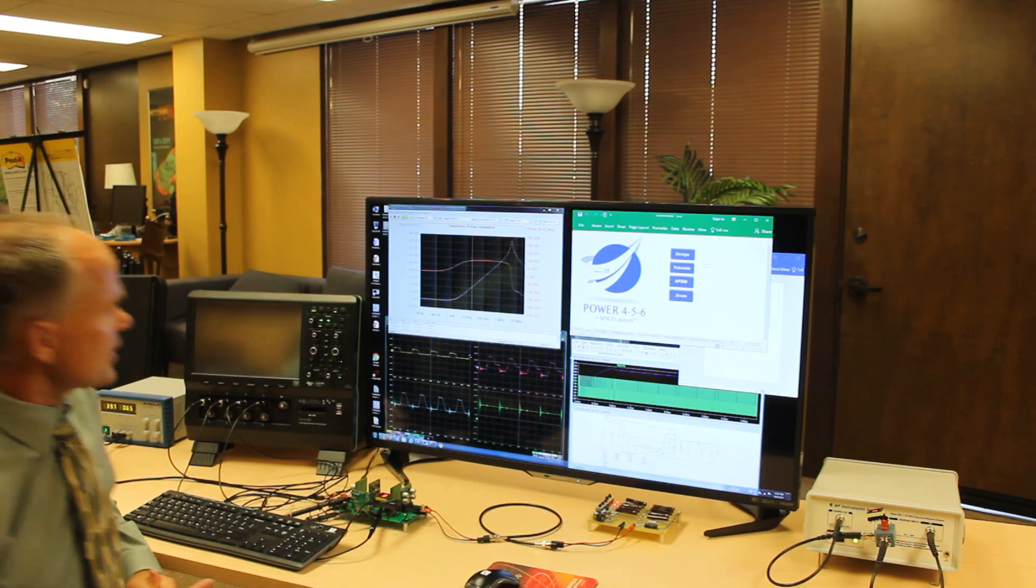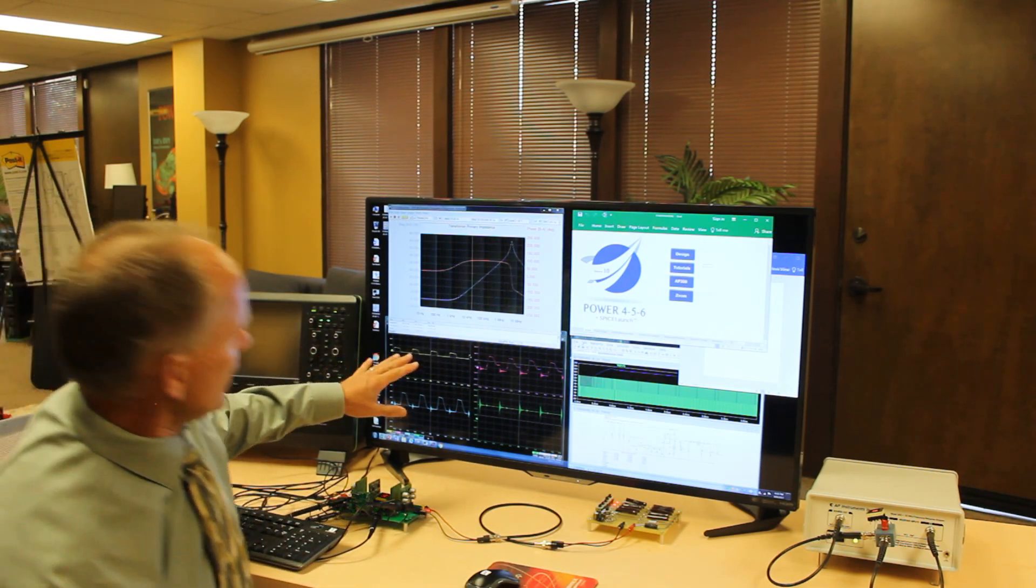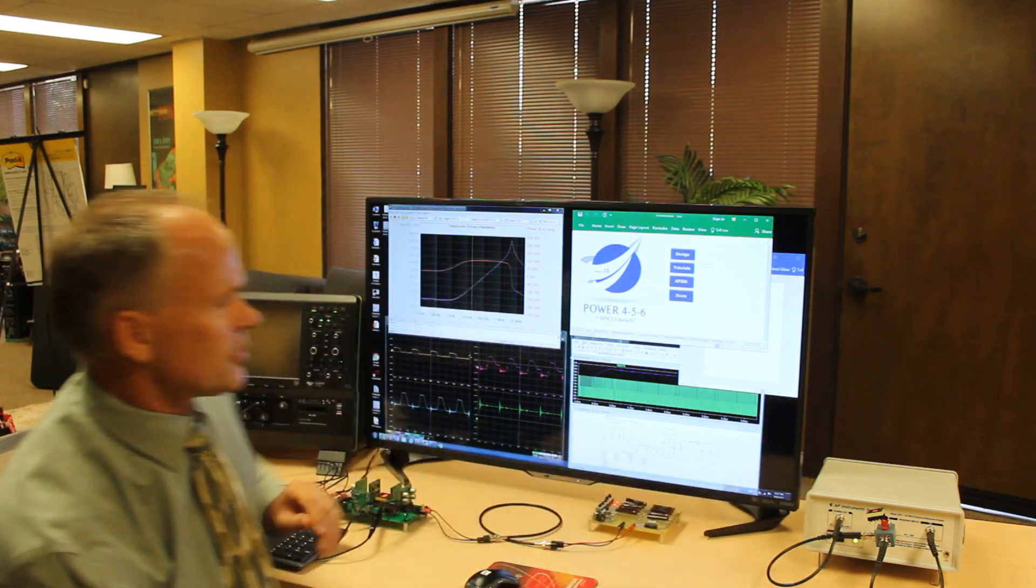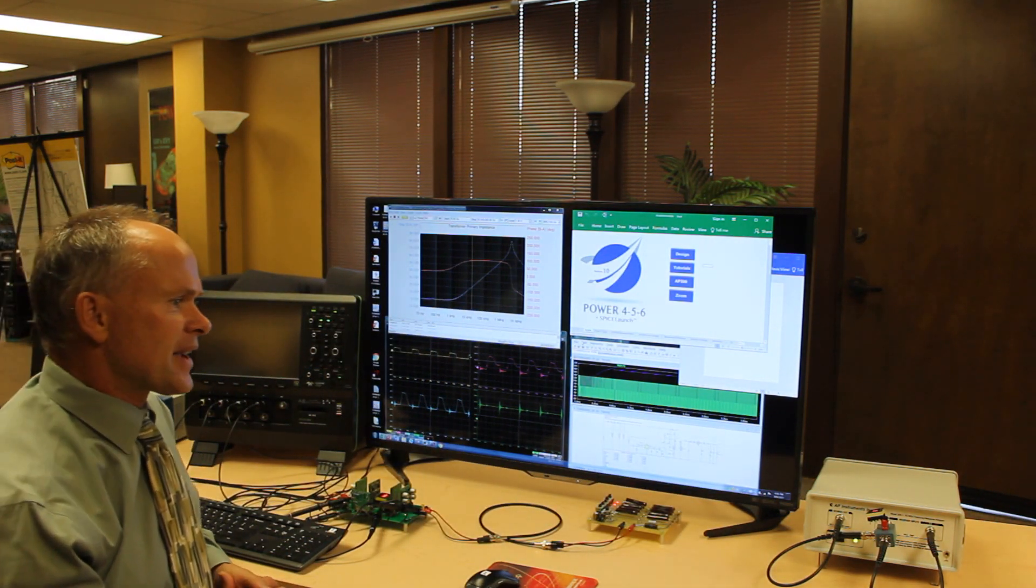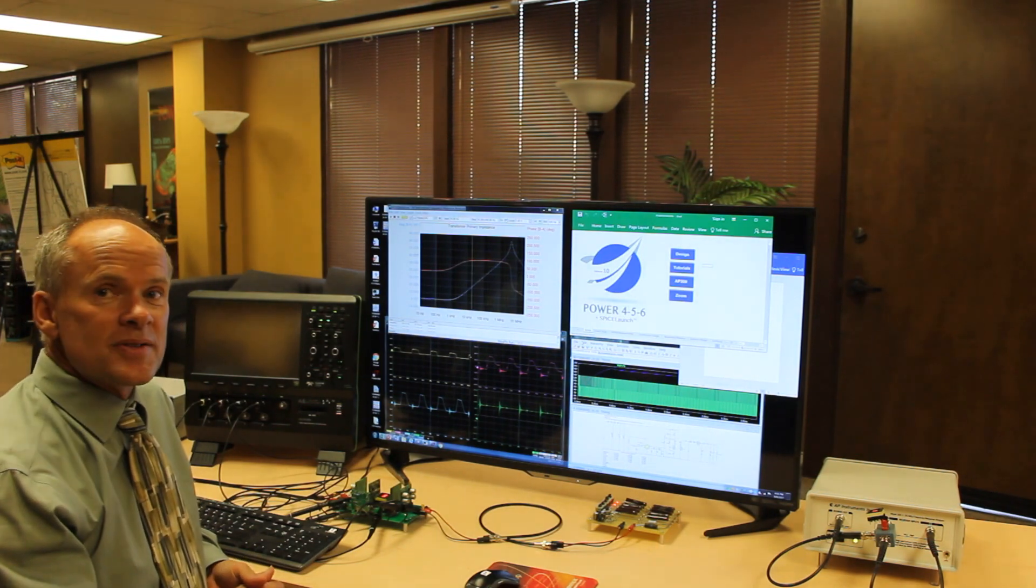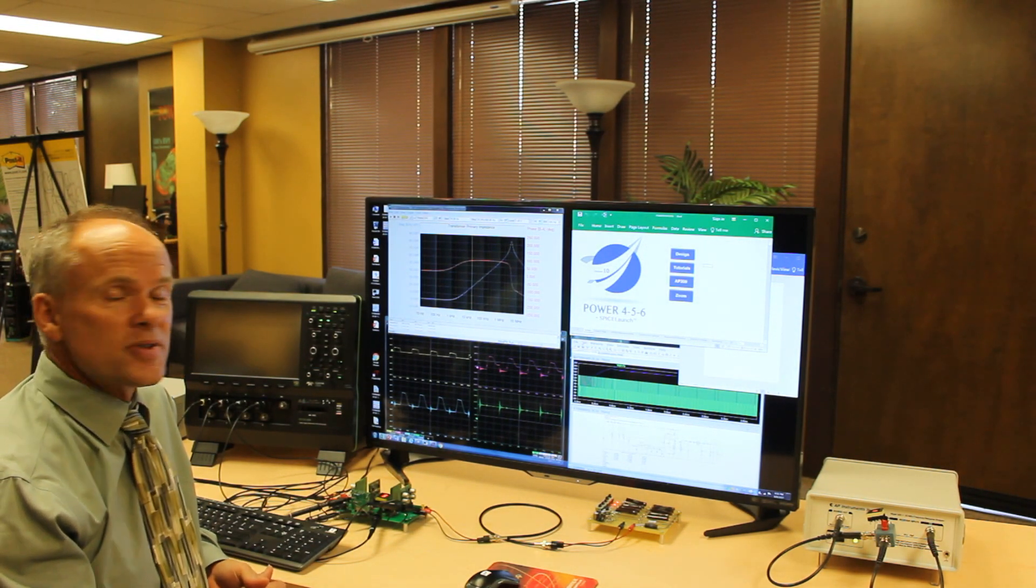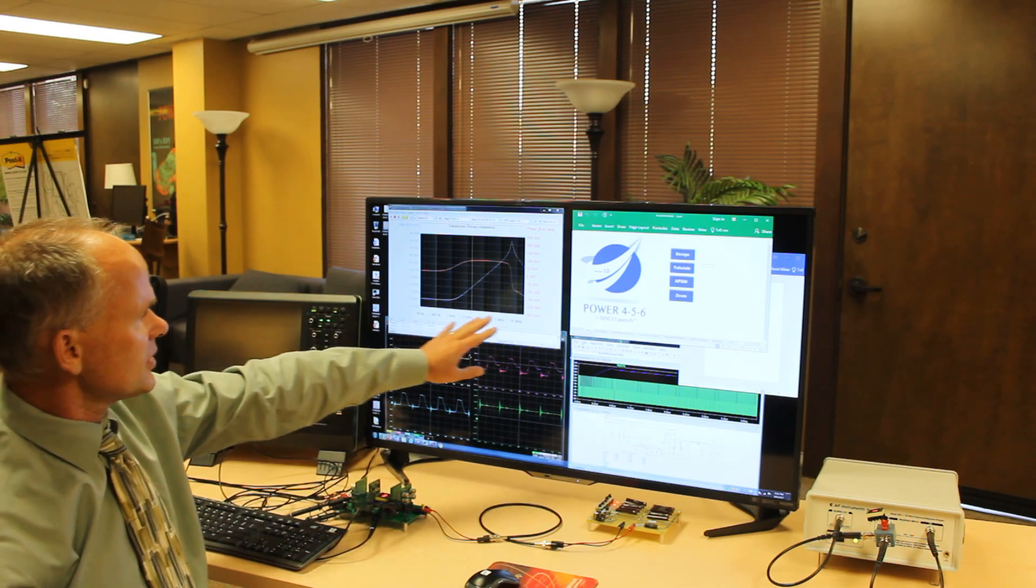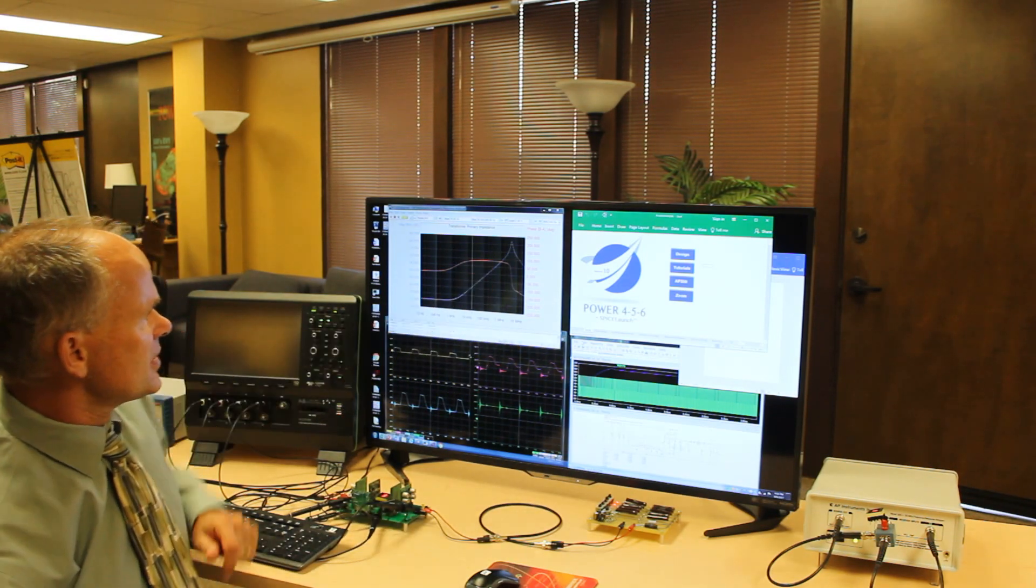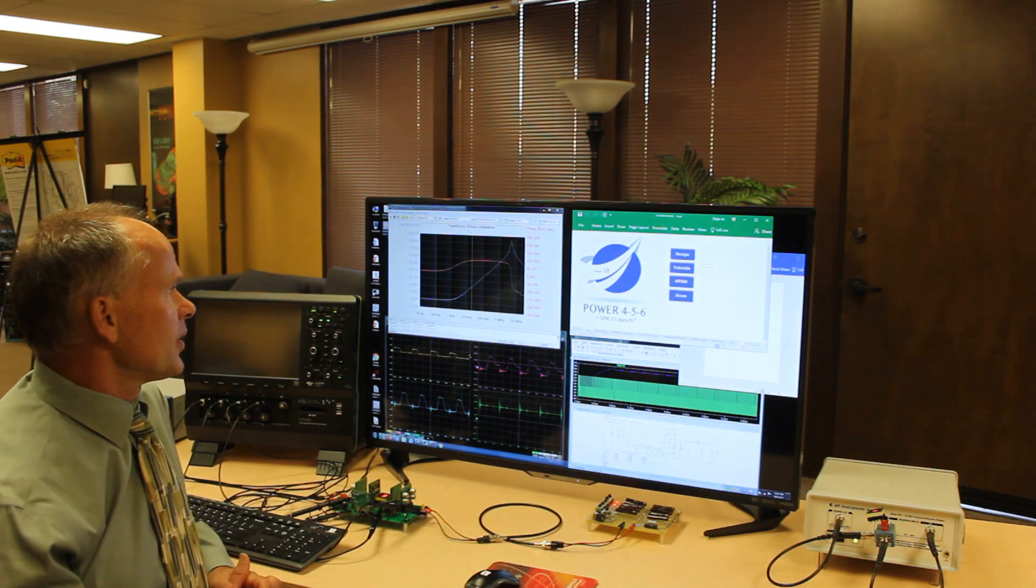At the same time that the scope is running, the computer in there is also running the AP300 frequency response analyzer and right now that's characterizing the primary impedance of the transformer. So we open circuit the secondary and we do a frequency sweep from 10 hertz to 30 megahertz and we watch the impedance of that frequency sweep.